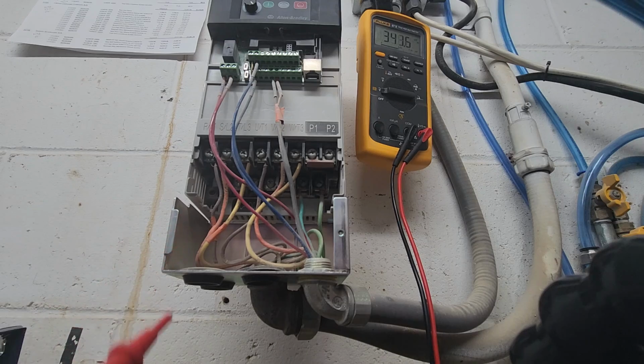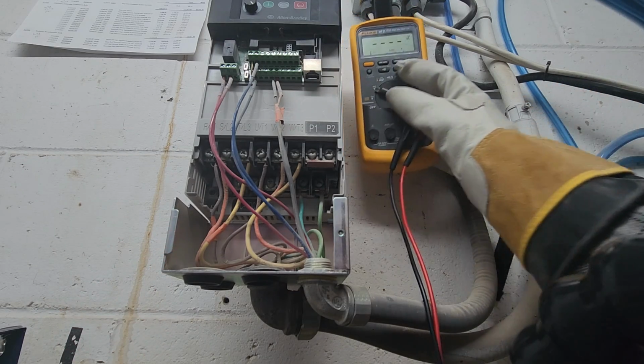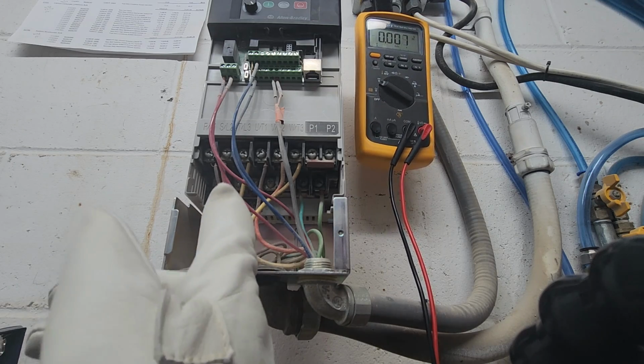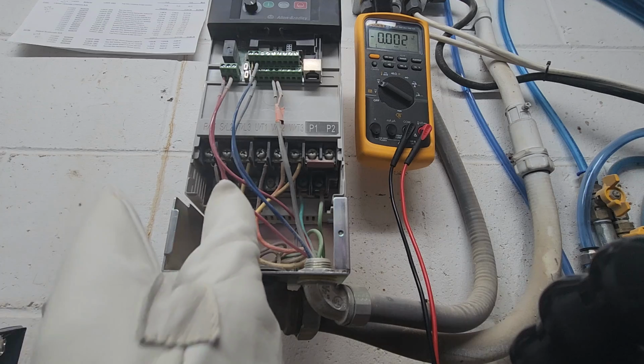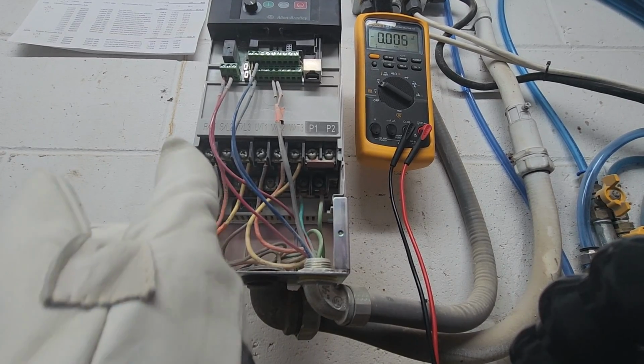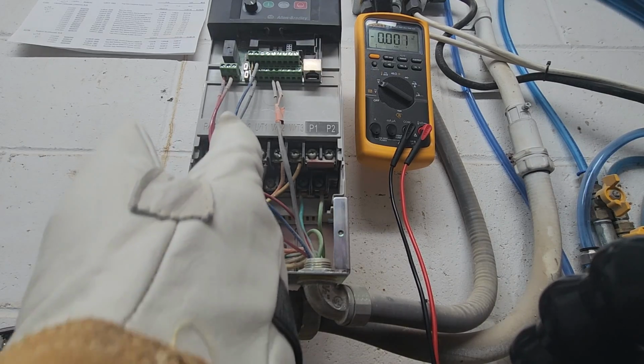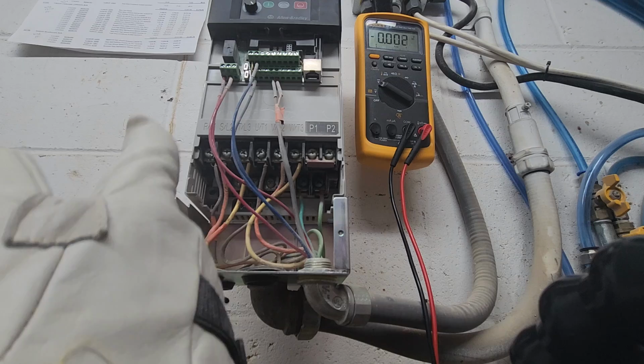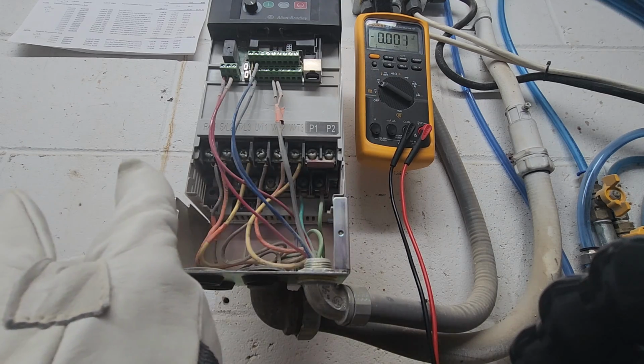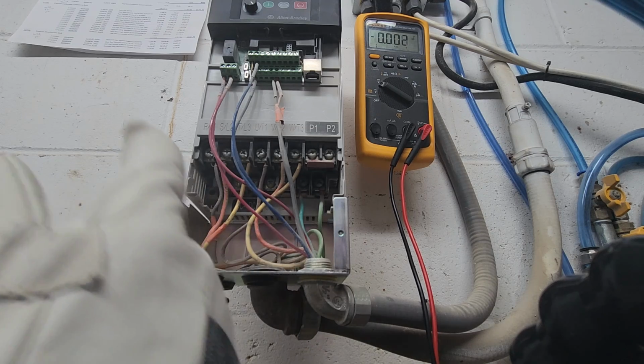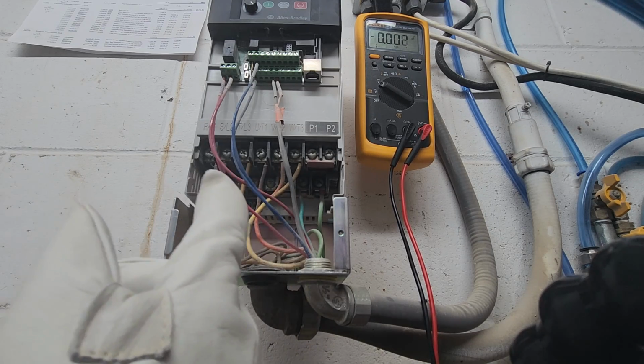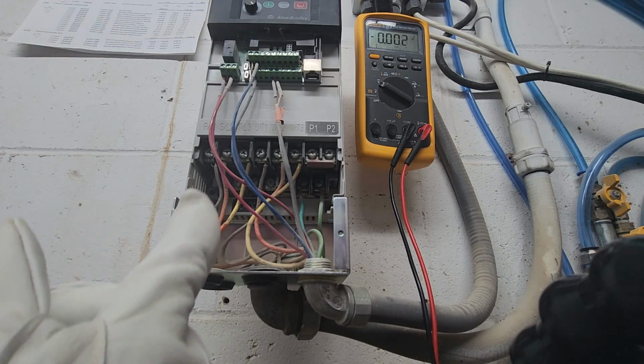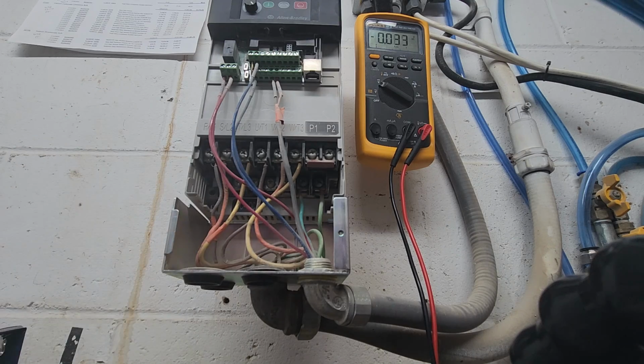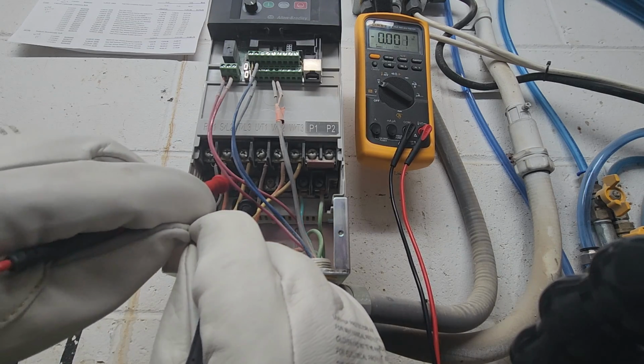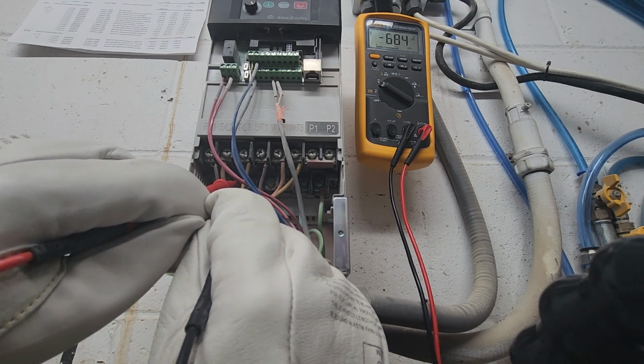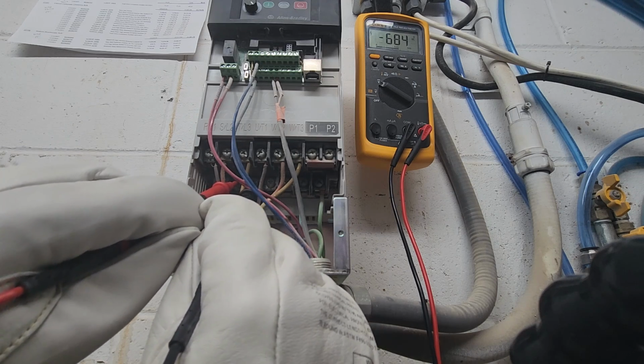Now we'll check our DC bus. So we'll put our voltmeter into volts DC. We should be reading on our DC bus 680 volts. Because you've got three sets of voltage potential between your L1 and L2 and L3. Your peak voltage will be between those three phases. That should all be 680 volts peak. It'll be like 480 volts times square root 2. So if our DC bus is at 680 volts roughly, that means that our bridge rectifier is probably working okay. So we'll go DC minus to DC positive. We've got 684 volts up there, which is perfect.